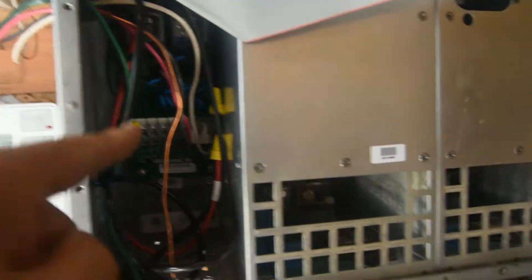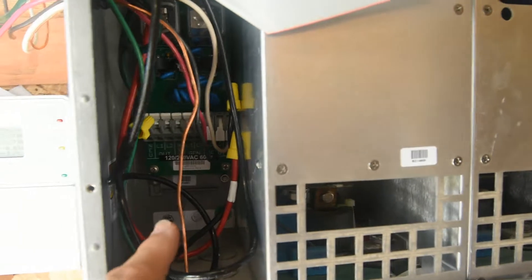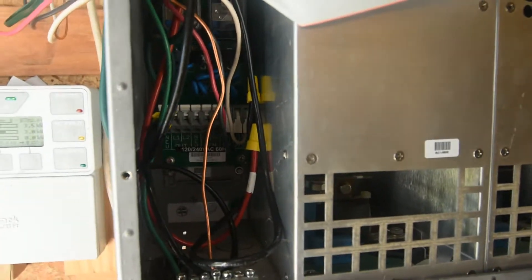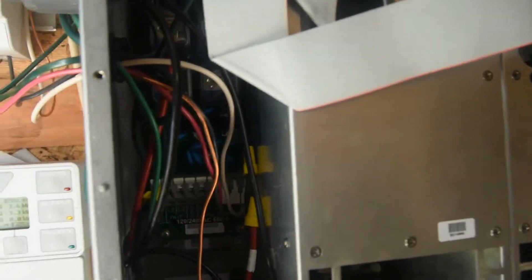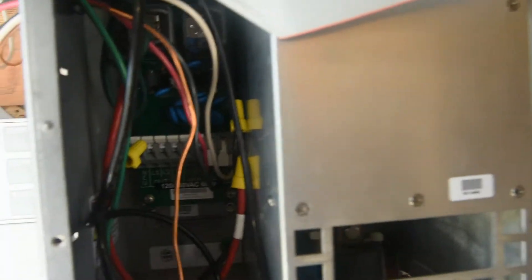Here I have number 10 wire coming in, and this is great — number 10 wire will support 7,200 watts. I never predicted to get this much out of this unit because this is a 4,000 watt unit. Together they can produce 8,000 watts supposedly, but for now the number 10 wire is fine. I'll show you why I'm doing it.